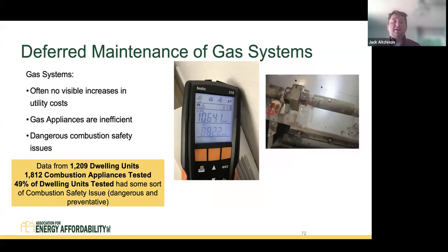Here's an example from one of my site visits a few years ago, where we had a combustion analyzer in a wall furnace and found carbon monoxide levels of 10,641 parts per million. To put that in perspective, 30 parts per million for 8 hours will set your CO alarm off; this level will cause CO poisoning very quickly. So this improperly maintained wall furnace may not show up on your utility bills in terms of inefficiency, but it will show up as a dangerous issue.